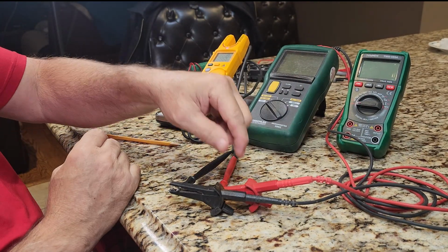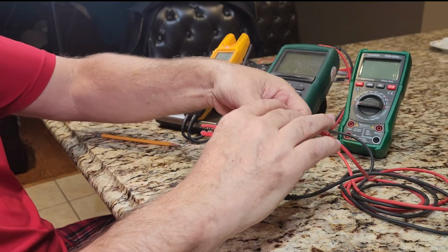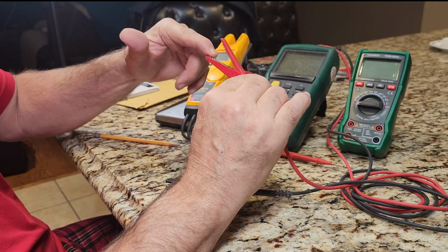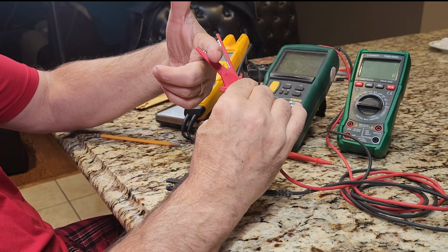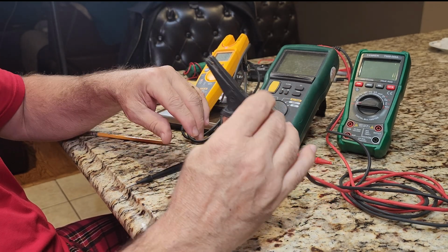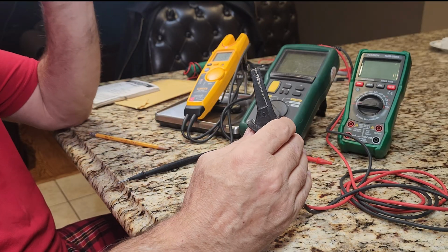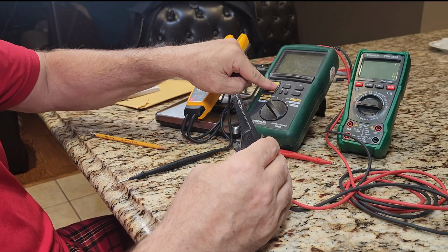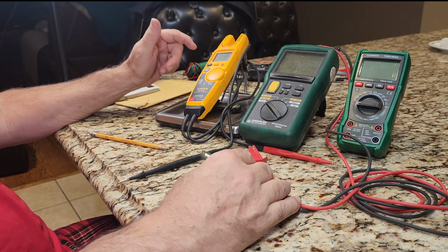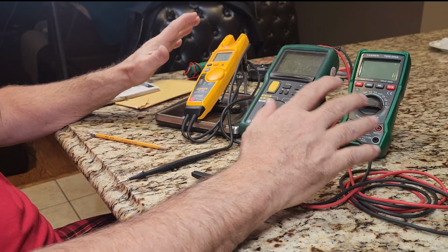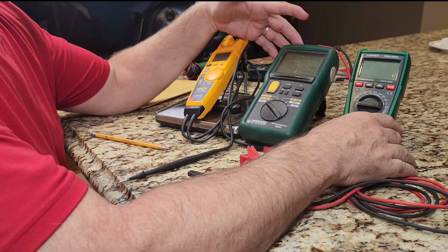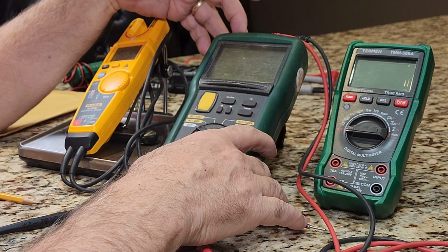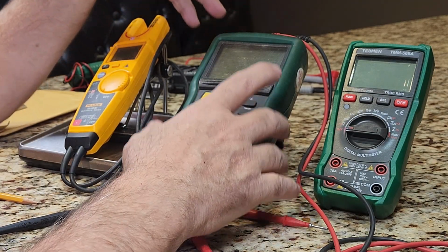So we can connect one lead on the insulation. You could literally take the wire and wrap it right around the whole insulation, on the outside of the insulation, and then the other one can be on the little conductor, usually a 2-aught conductor, inside of a high voltage cable. You can grab onto that, and then you do your tests, and that's the difference. So in a nutshell, it's basically the same principle, but you've got the ultimate granddaddy that has the ultimate 1,000 volt capability, commercial, industrial. It's highly insulated.